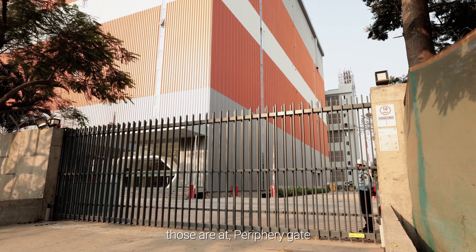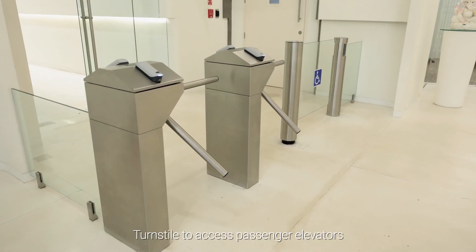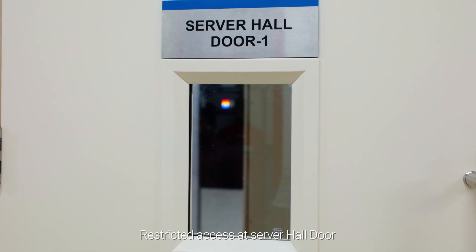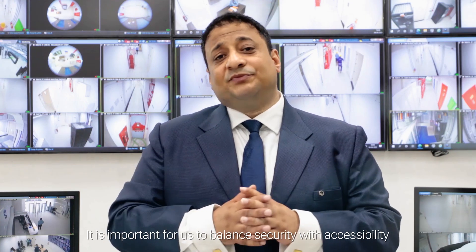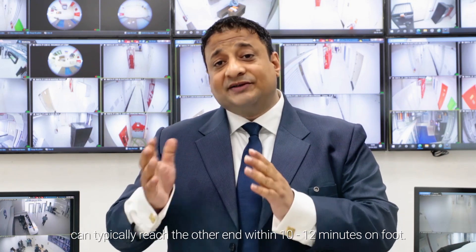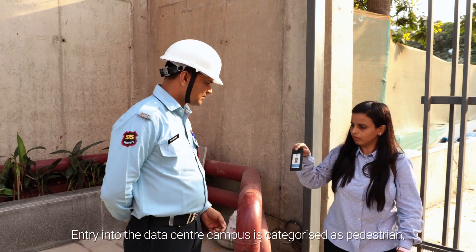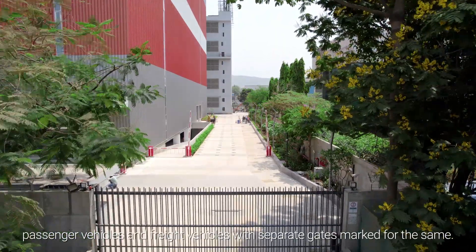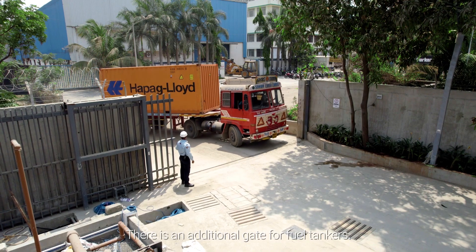Those six levels are: periphery gate; lobby area for man movement and loading bay area for material movement; turnstile to access passenger elevators; security check on the server hall floor; man traps; and restricted access at the server hall door. Entry into the data centre campus is categorized as pedestrian, passenger vehicles and freight vehicles with separate gates marked for each, plus an additional gate for fuel tankers.